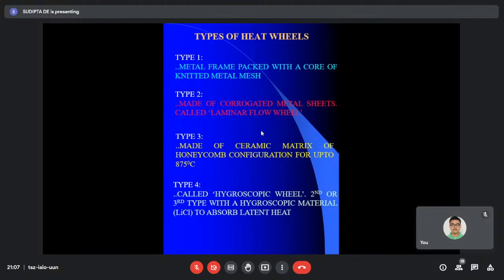Okay, fine. So with these four different types of wheels, we have found that the first one is simple, but heat transfer is also low. I'm just mentioning in short so that you can note it. The second type, the contamination is less. The first type, the contamination is also high. It is the low cost and simple option, the type 1. Type 2, low cost, simple option with lesser contamination but less heat transfer too, so the performance is poor.